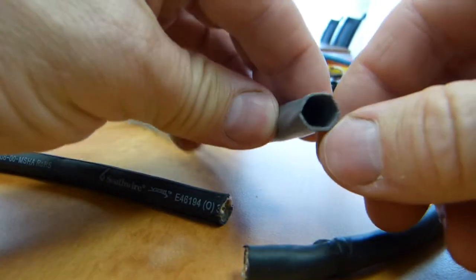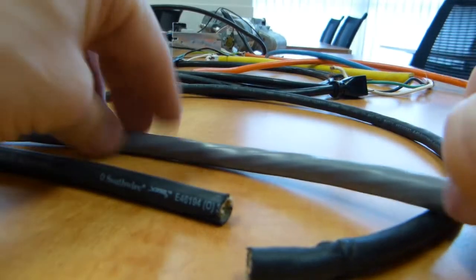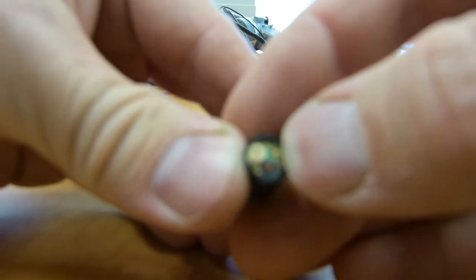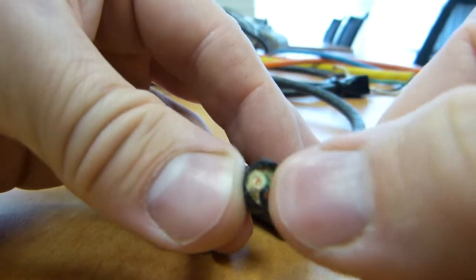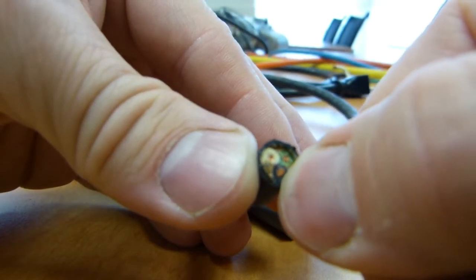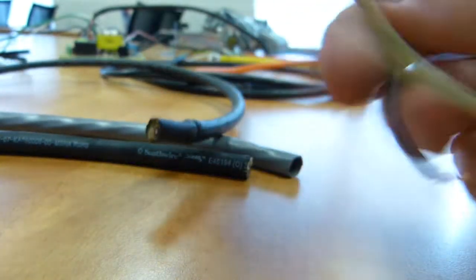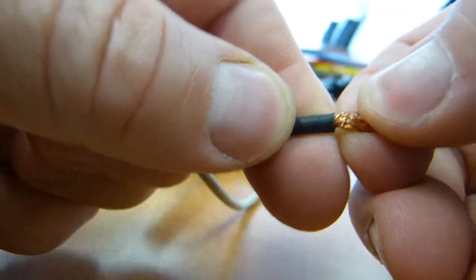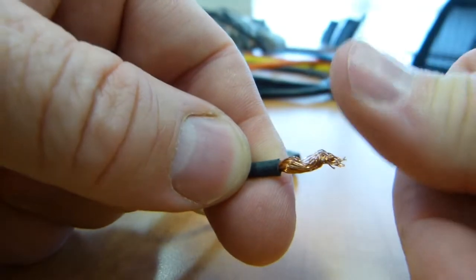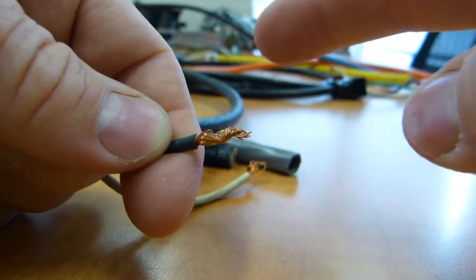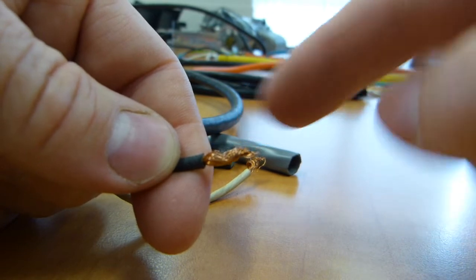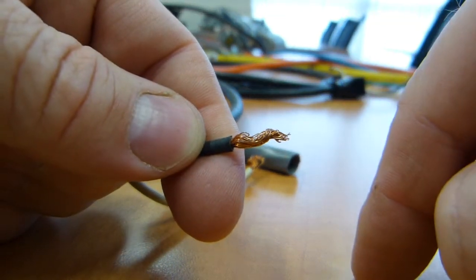This one is obviously thicker, bigger conductors were inside, and has a higher temperature rating. So as the wire size is increased, the conductor size is increased, they can put more amps through the conductor, through the wire inside the conductor there. So the skinny wire, few amps, big wire, more amps. So they know they can put maybe 15 amps through this copper conductor. If they increase this size, they can put more amps through it. But if the temperature increases, then the amps need to be going down.